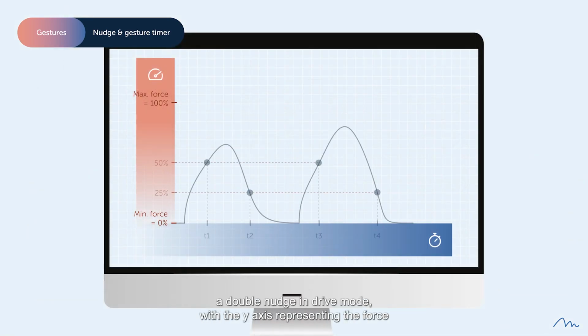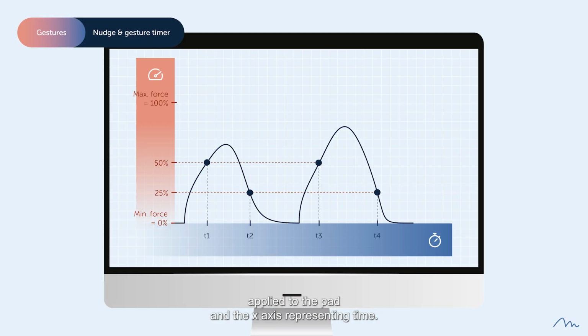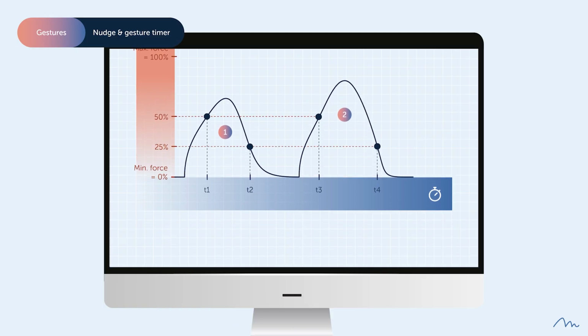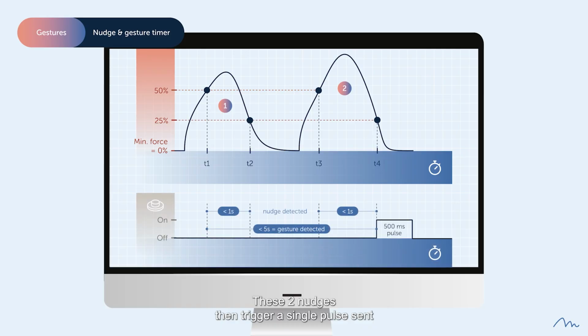This example graph illustrates a double nudge in drive mode, with the y-axis representing the force applied to the pad and the x-axis representing time. You can observe a rise in force when pressing, the release where the first nudge is detected, followed by another activation and deactivation of the pad. These two nudges then trigger a single pulse sent to the wheelchair electronics, which executes the action as configured, for example, toggling the direction.